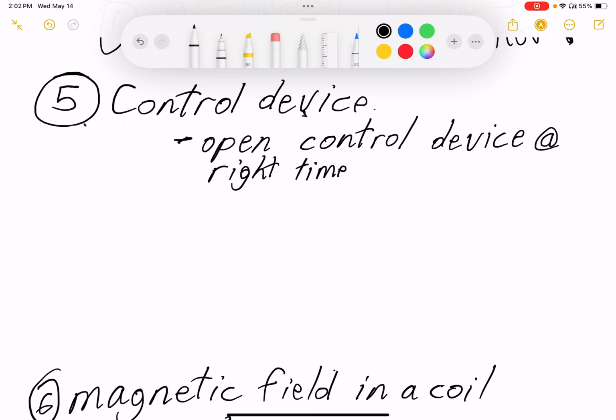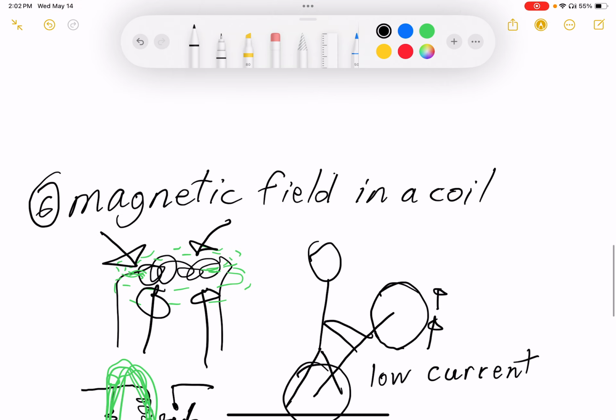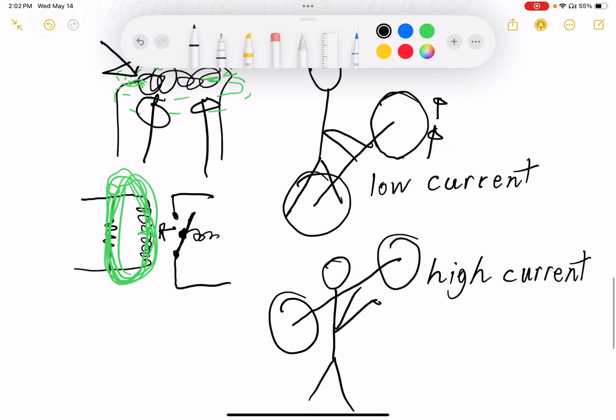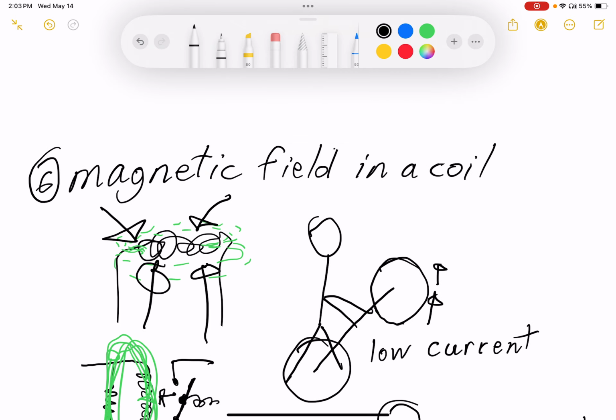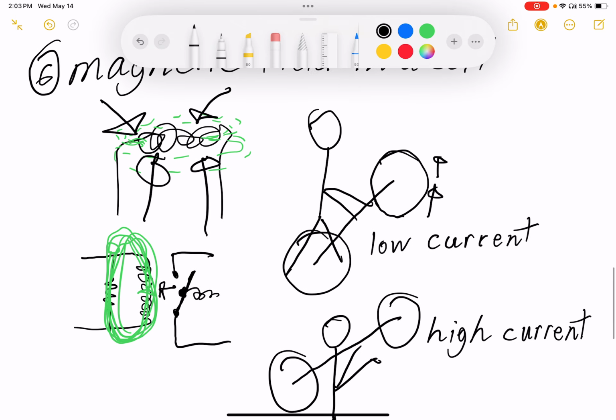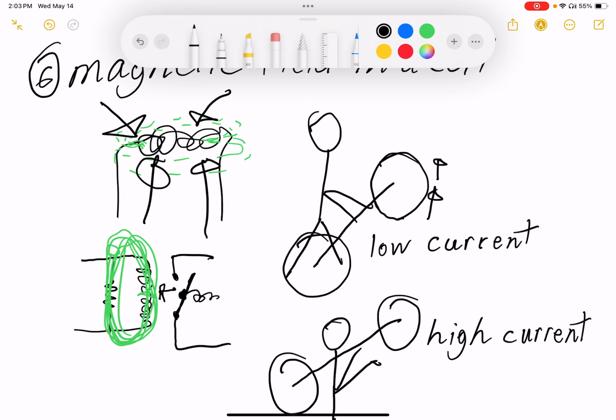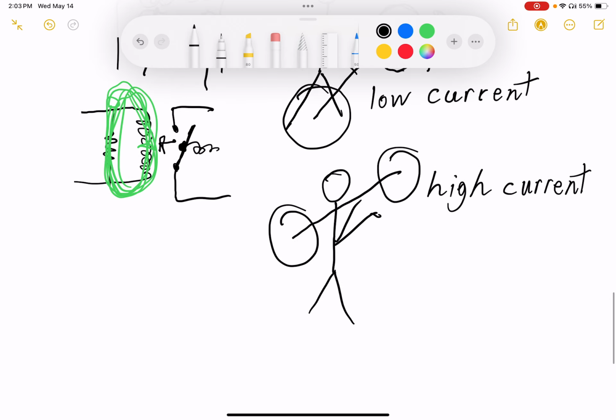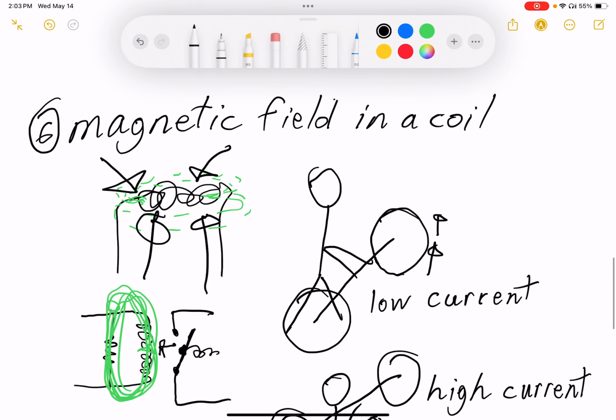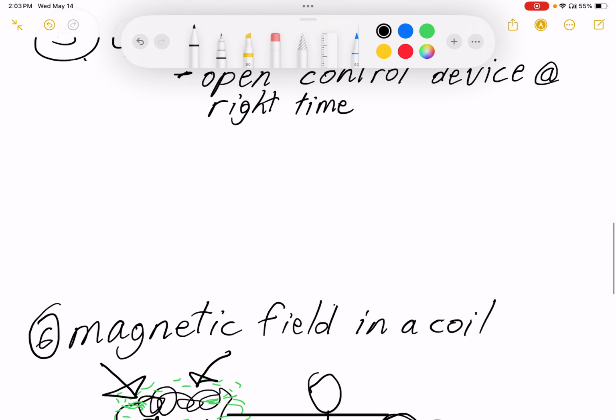To open the control device at the right time, we also need to build the correct magnetic field in that coil. As that magnetic field is building and that current is flowing, you don't want the magnetic field at maximum for too long, because that's like making a weightlifter stand there holding the weight above their head for too long. You want it to build the magnetic field and then drop it right away so it doesn't have to do excessive work.